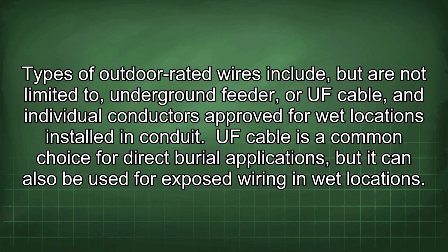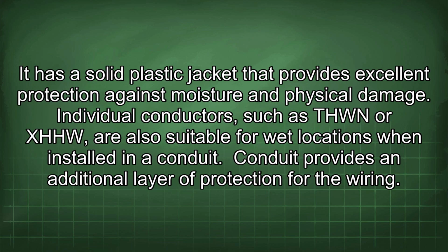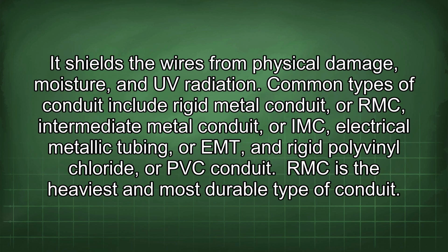UF cable is a common choice for direct burial applications, but it can also be used for exposed wiring in wet locations. It has a solid plastic jacket that provides excellent protection against moisture and physical damage. Individual conductors, such as THWN or XHHW, are also suitable for wet locations when installed in a conduit. Conduit provides an additional layer of protection for the wiring. It shields the wires from physical damage, moisture, and UV radiation.